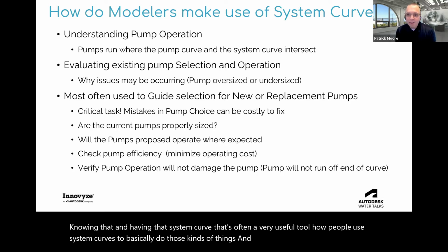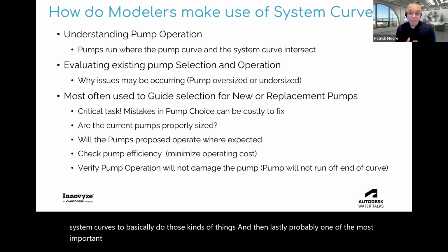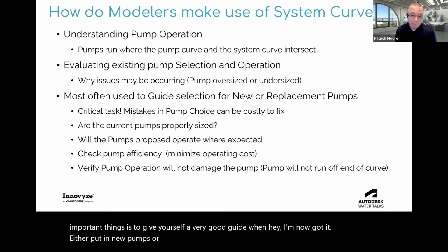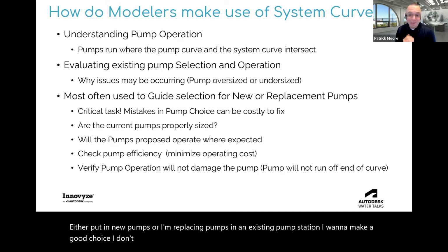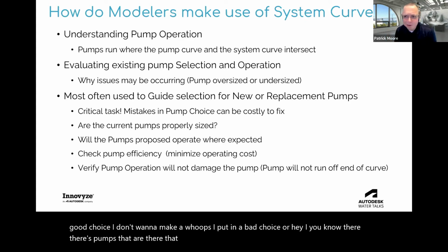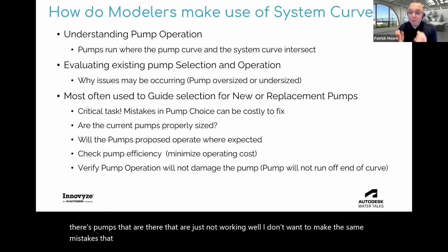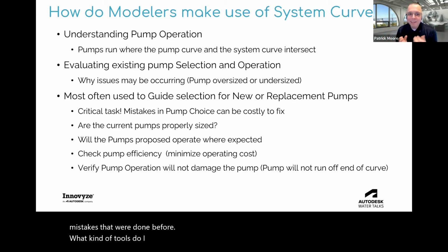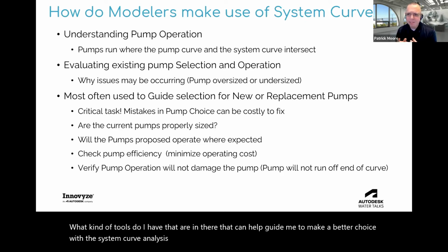And then lastly, probably one of the most important things is to give yourself a very good guide when I'm now going to either put in new pumps or replace pumps at an existing pump station. I want to make a good choice. I don't want to make a bad choice, or there are pumps there that are just not working well. I don't want to make the same mistakes that were done before. What tools do I have that can help guide me to make a better choice? Well, the system curve analysis is really the best tool that gives you that information so that I can make the best choice.